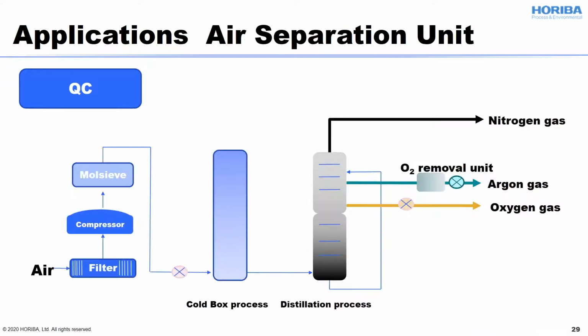And the trace hydrocarbon needs to be monitored for the product stream after the distillation process. This is to eliminate the risk of hydrocarbons combining with the liquid oxygen to become an explosive mixture. Ensure quality of all the product streams. Measurement range is 0 to 10 ppm.